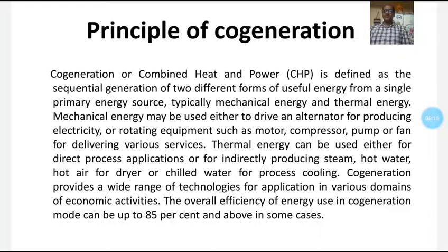If waste heat recovery systems such as a waste heat recovery boiler are there, and it is 85% efficient, then the waste energy from the first cycle can be regained, so we can recover more than 34% of heat from the waste of the first cycle.